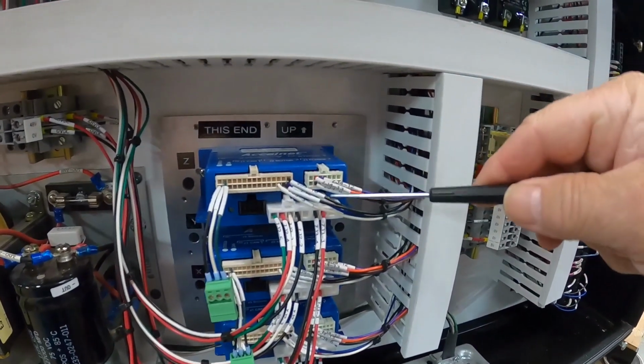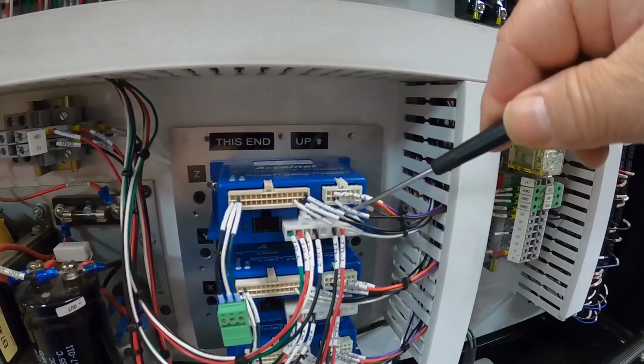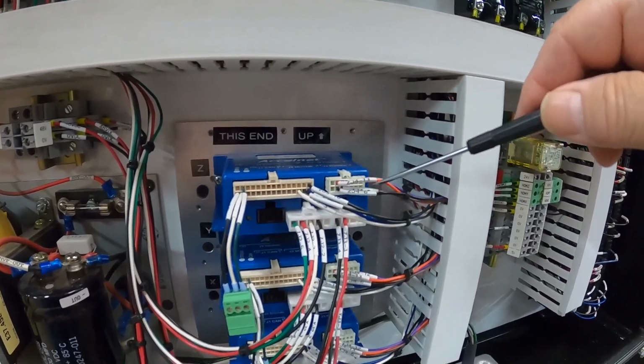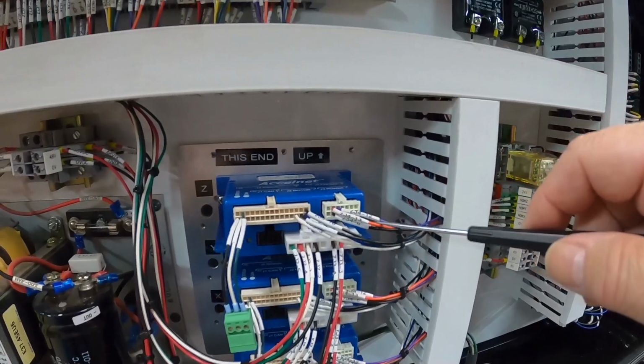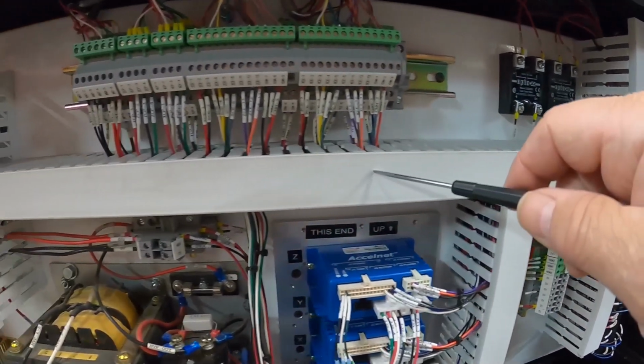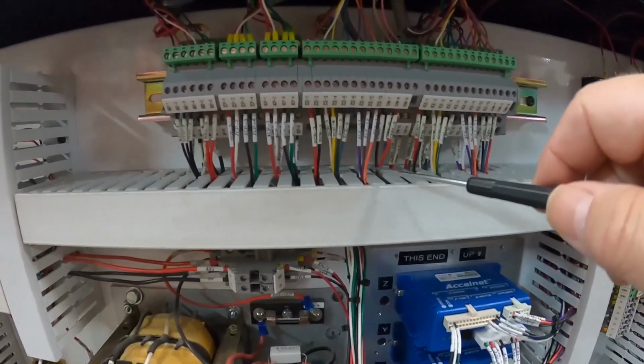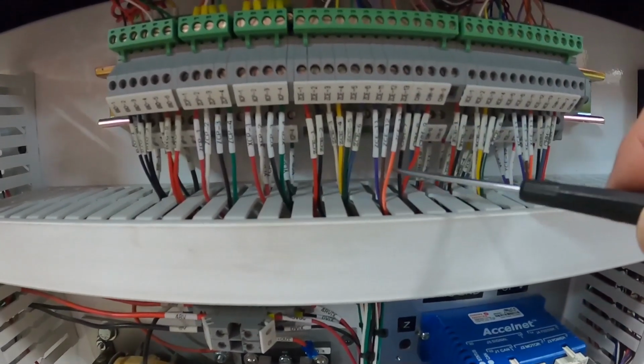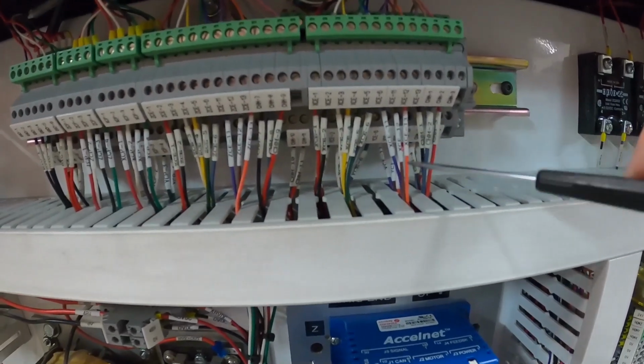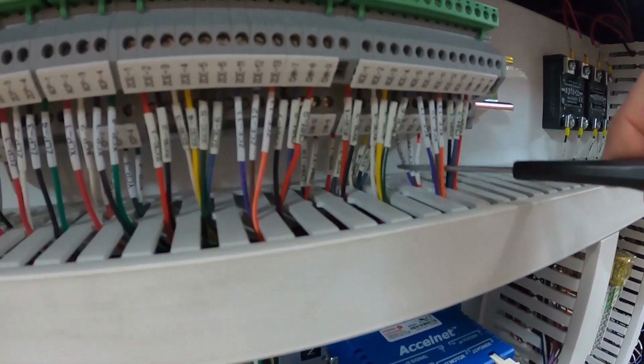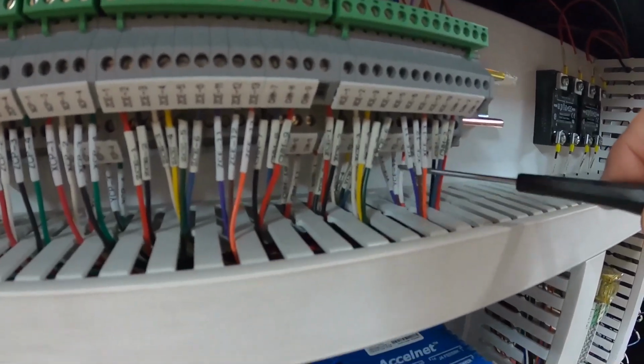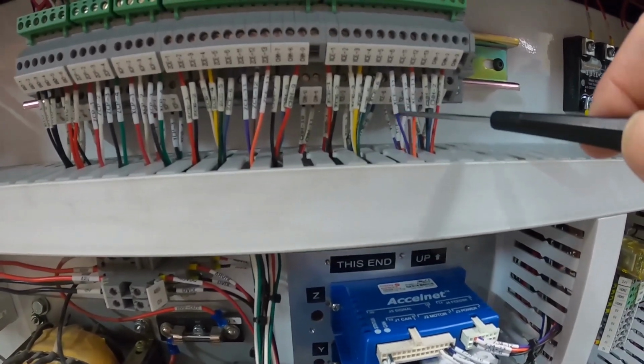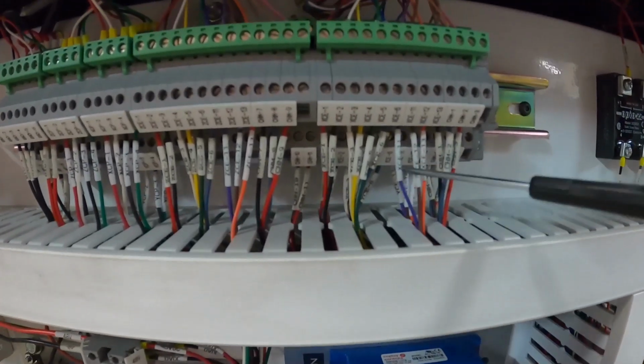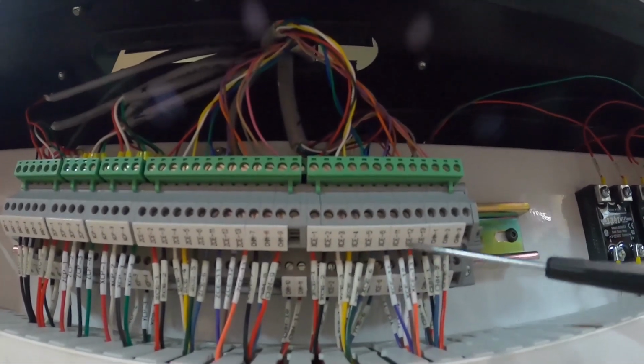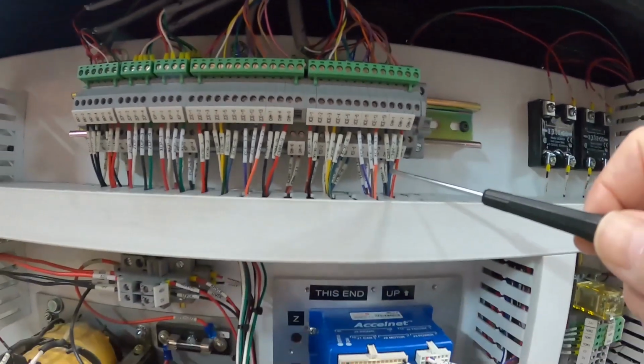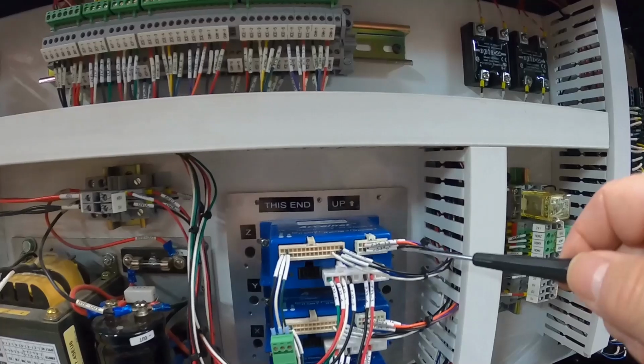So these are the Hall effects. There's a 0 volt line here, and then there's a U, V, and W Hall sensor. These lines go over through this cable track and up to the respective location - there's the Z right there, the X right there, and behind back here is the Y lines and the Hall effects. You can see they're labeled, and the label on the wire matches the label on the terminal block. So that's the Hall effect line.